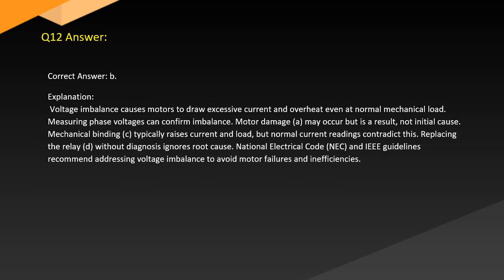Answer. Correct answer: B. Explanation. Voltage imbalance causes motors to draw excessive current and overheat even at normal mechanical load. Measuring phase voltages can confirm imbalance. Motor damage may occur but is a result, not the initial cause.